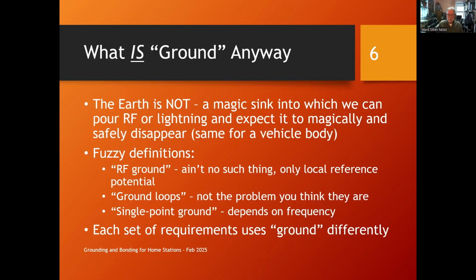Also, single point ground. Single point means electrically small, so that everything connected to this structure, whatever it is, is at the same voltage. So that's primarily a concern for electricians who don't want to have ground loops, so they connect everything to this single point. And it's electrically small. What does that mean? It means much, much, much less than a wavelength. What's a wavelength at 60 hertz? 5 million meters. Okay, so you can have something the size of a building or a football stadium, and still it's electrically very small. So what you want is to be careful when you use that term.